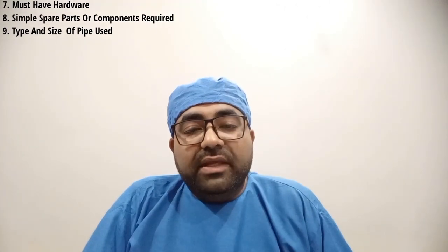The most common two sizes of tubings that require more repairs are the 6 mm by 4 mm tube and the 4 mm by 2 mm tube. I would strongly suggest you should have at least these two sizes compulsorily in your dental clinic. In our next video, I am going to share tips and tricks to help you change the whole tubing of your dental chair yourself, and I will demonstrate which tubing is used for what along with their common locations.